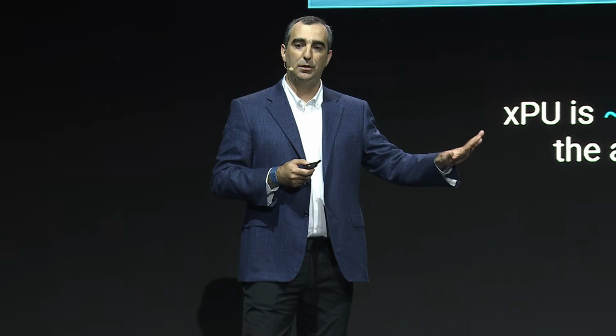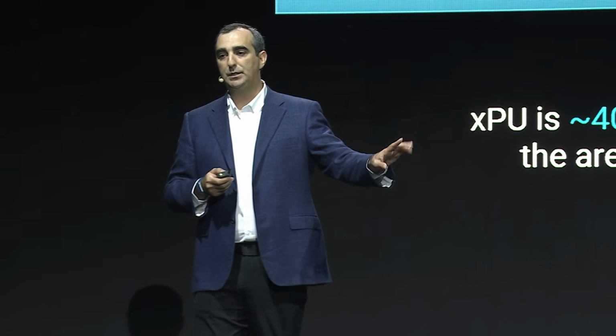Now aggregate that across a 1 megawatt rack. You can save 50 kilowatts of power by going to this architecture. Think about that for a second. Four years ago, racks didn't consume 50 kilowatts. We're saving that much power by changing to this architecture. And this has happened—this isn't happening, this has happened. But with this comes enormous challenges.